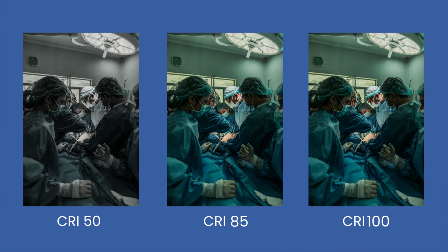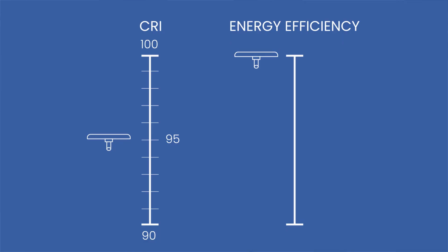Therefore, it appears to be only a scholastic exercise to attempt and require a higher color rendering value. We must also take into consideration that surpassing a color index value of 95 significantly diminishes energy efficiency. Hence, it is important to acknowledge that for each index value above 95, a considerable loss in energy efficiency occurs. Therefore, a surgical lamp in the operating room ought to be displaying a color rendering index between 90 and 95.